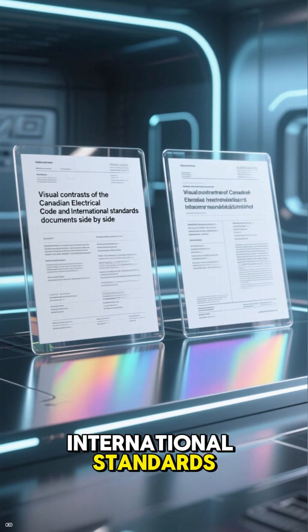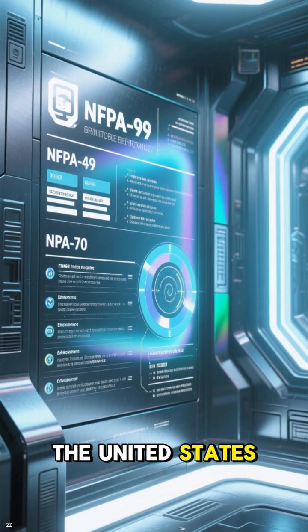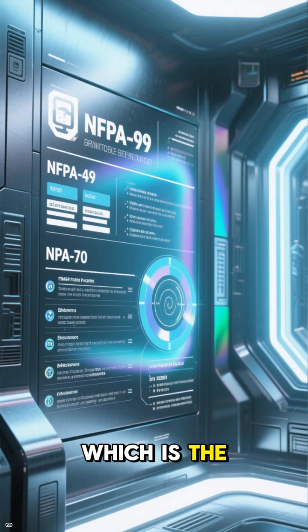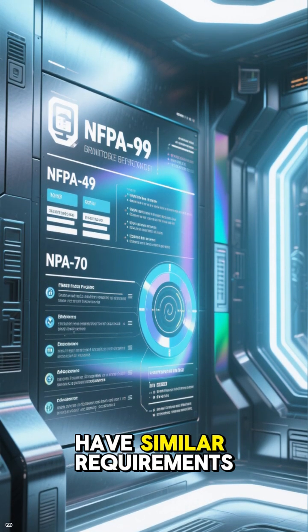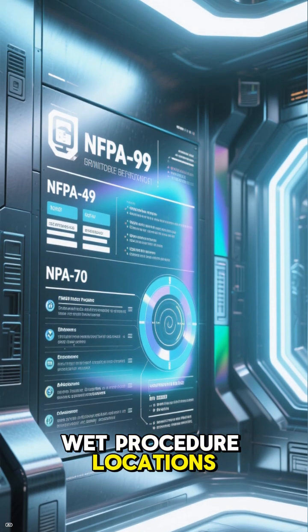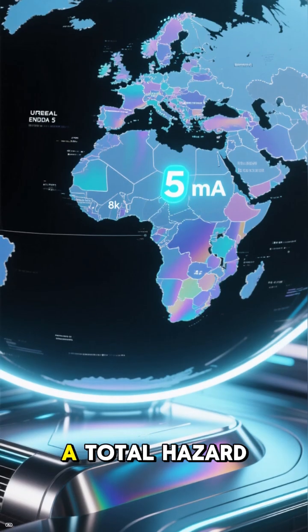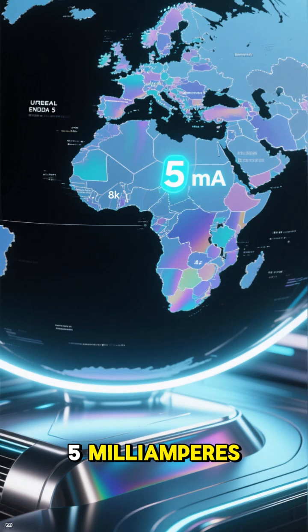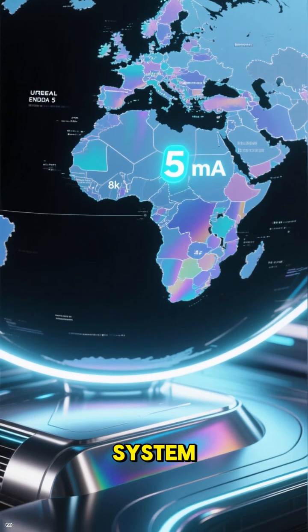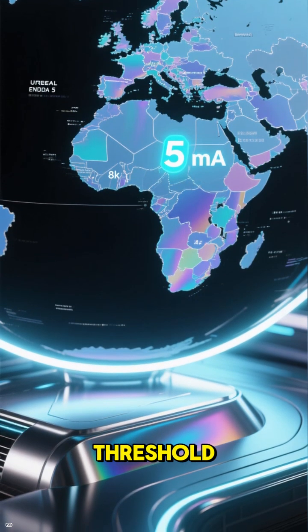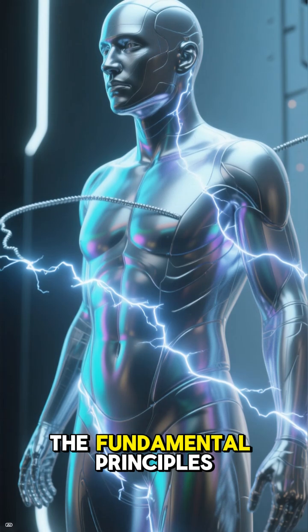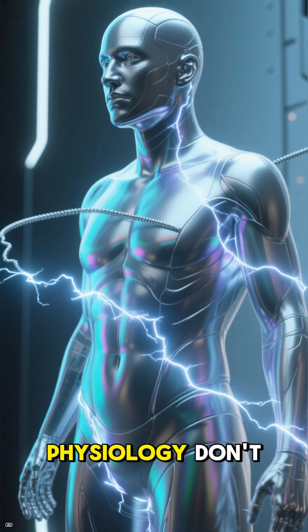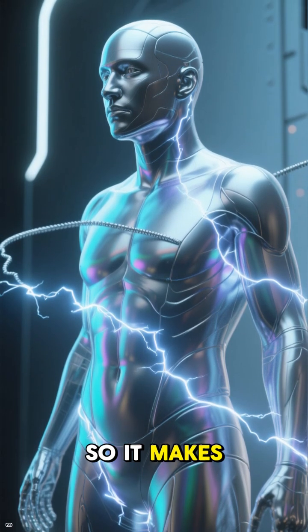It's interesting to compare this with other international standards. For example, in the United States, NFPA 99 and NFPA 70, which is the National Electrical Code, have similar requirements for isolated power systems in what they call wet procedure locations. They also specify a total hazard current limit of 5 milliamperes for the complete system. This shows a global consensus on this safety threshold. The fundamental principles of electricity and human physiology don't change at the border, so it makes sense that the safety standards are aligned.